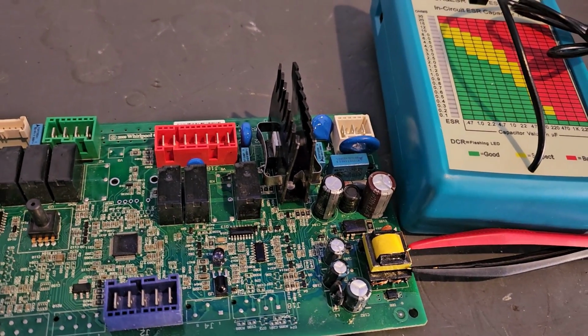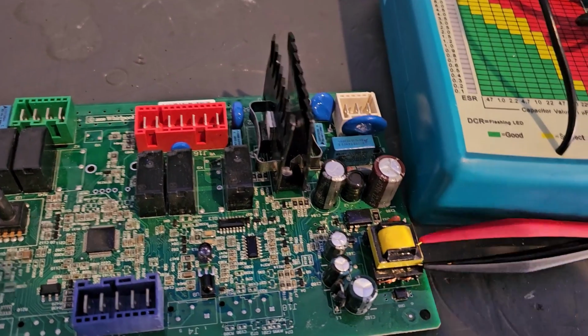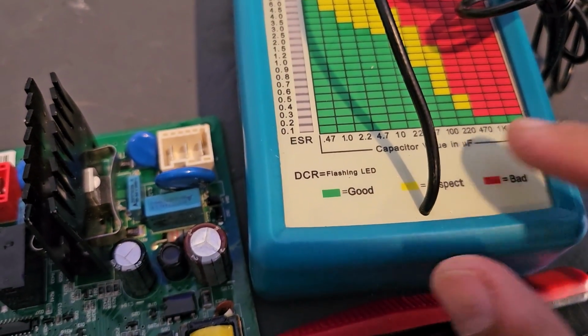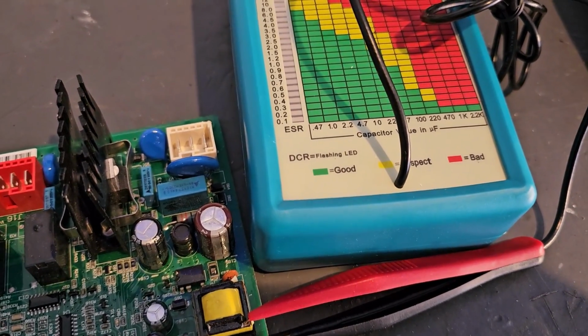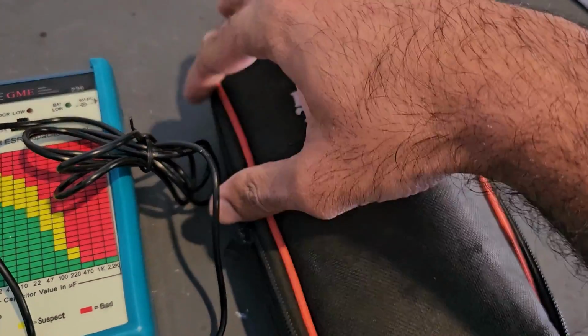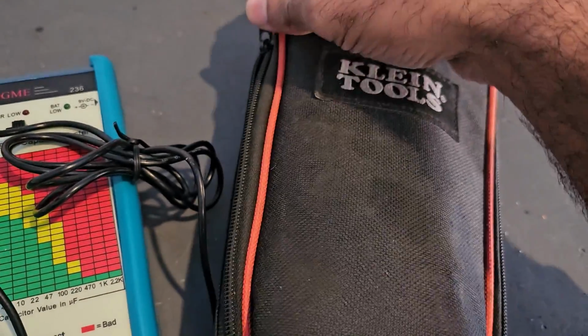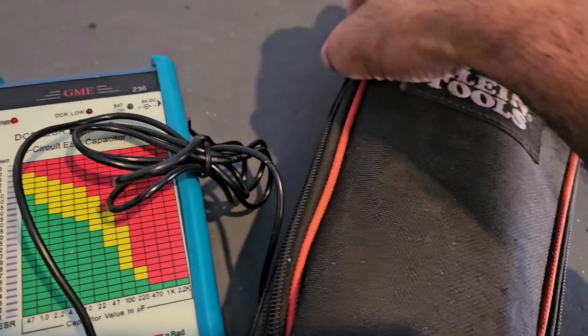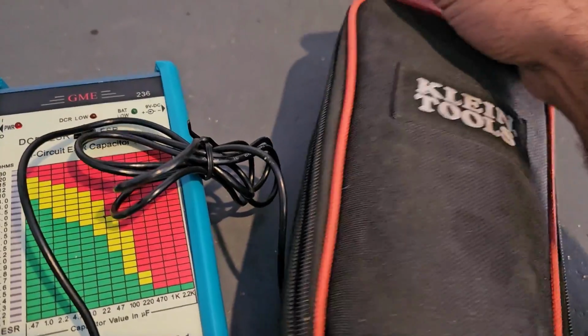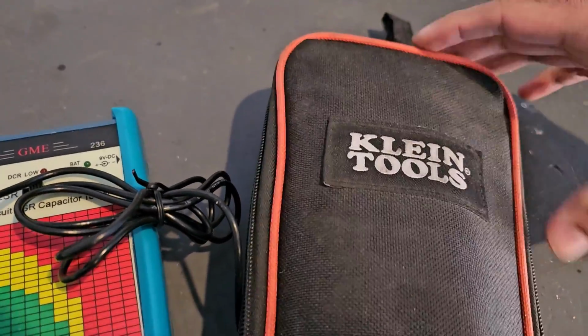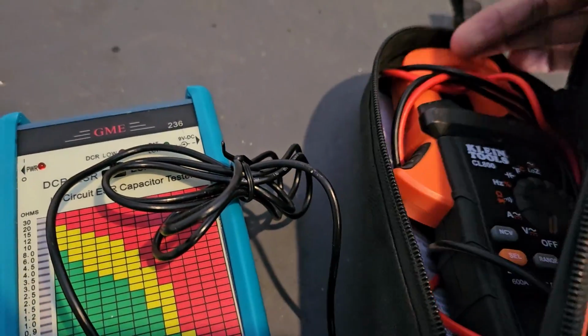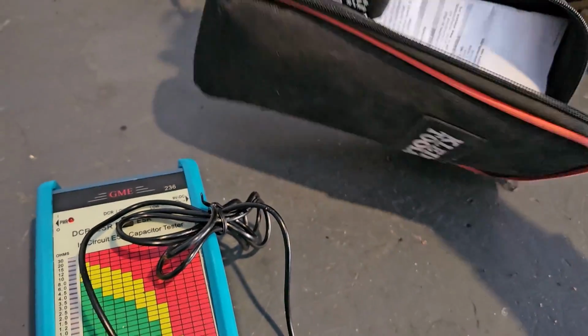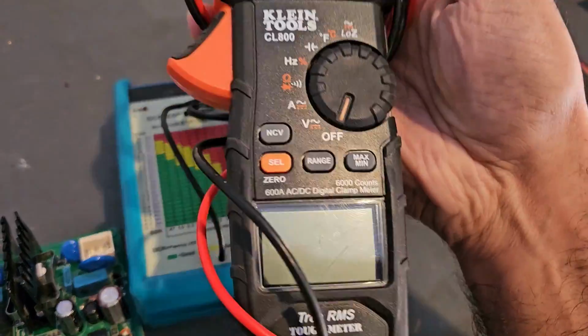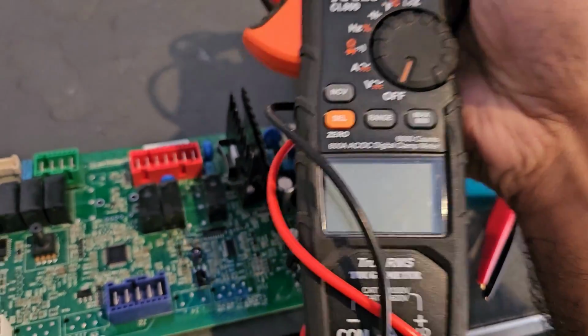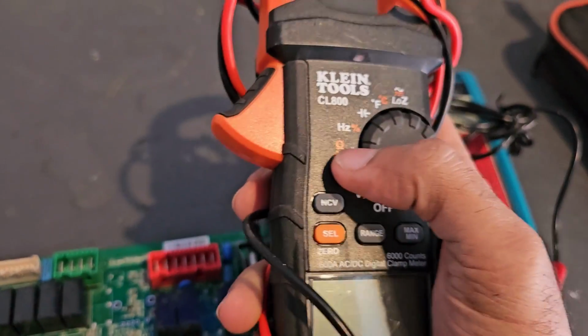Now, you may be wondering, what about the capacitance? So this value right here in microfarads, that's the ability of the capacitor to store charge. Now, pretty much any multimeter that's worth anything has a value for capacitance. However, to actually use that value, that capacitor has to be taken out of circuit. So to troubleshoot capacitors based on that capacitance value is very difficult, because that would involve taking them out of circuit and then actually seeing what their capacitance is.